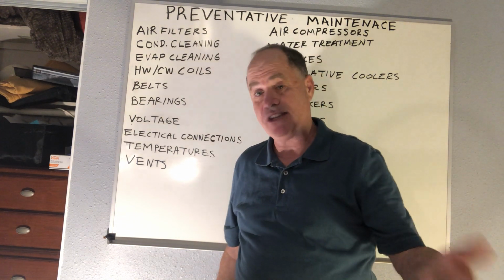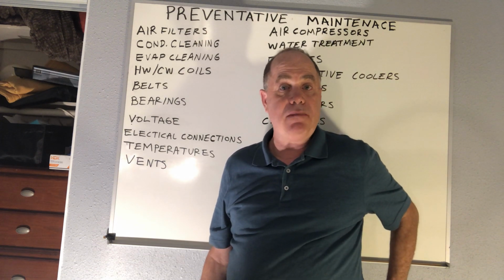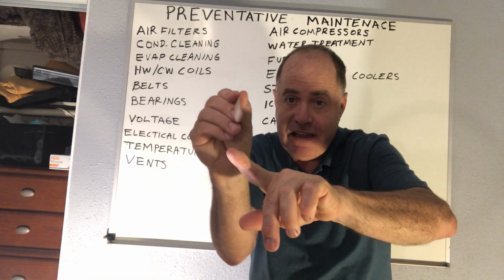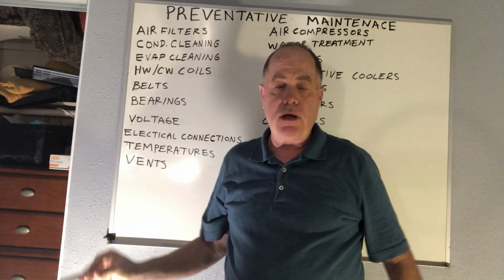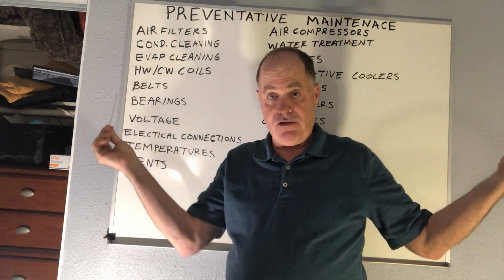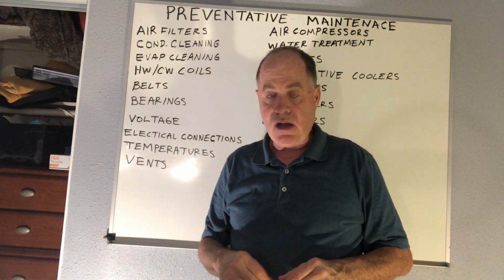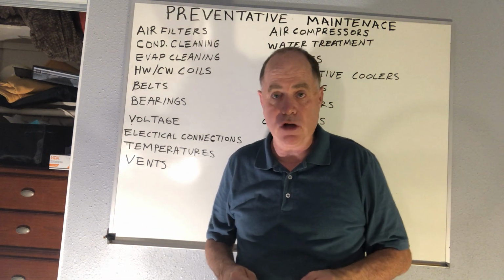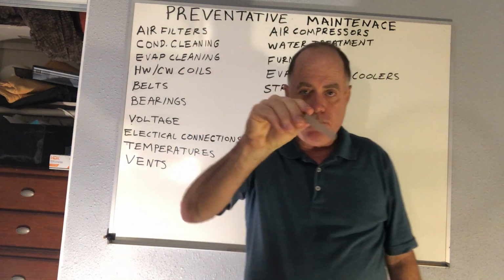Also, your thermocouples in the standing pilot can get blackened over time, and they may not hold the pilot. And sometimes if you just get that in there and then shine that up, it'll work for you and even repair the system. I've had that just be the problem and done that, and certainly the furnaces have gone at least another year or so to get me out of the woods to finish the service call. So that's something to do on maintenance that I'll do this fall for my furnaces, polish my flame sensor on it, okay? So there's a tip.